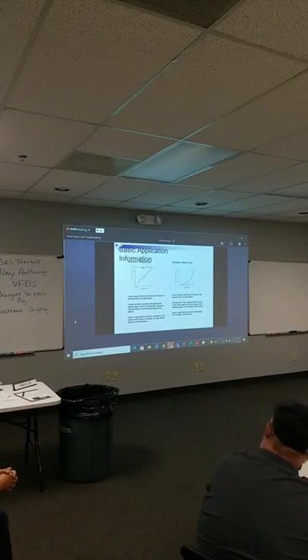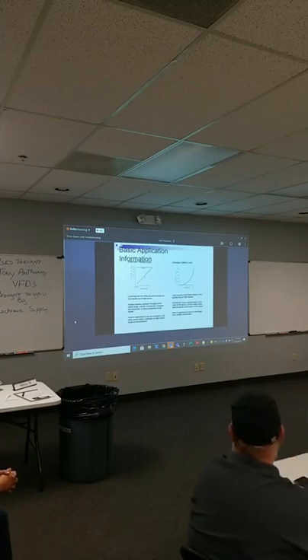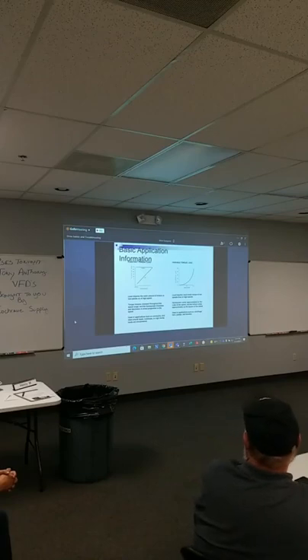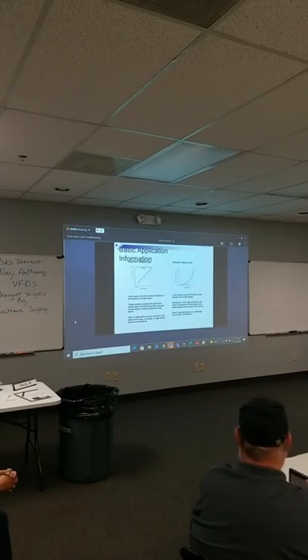But that's why, from back in the day, you see bypass units. Who still sees bypass units? We all do. We don't need them anymore, but we still see them. The problem is, bypass units came into play because of this energy savings. In the 80s and 90s, when drives first came out, if you got six months to a year out of a drive, you were happy, because you saved so much money.